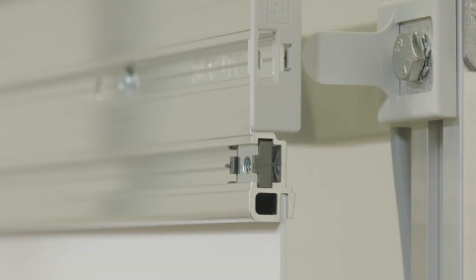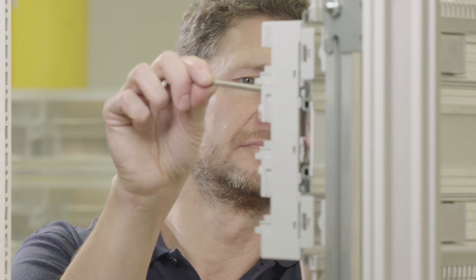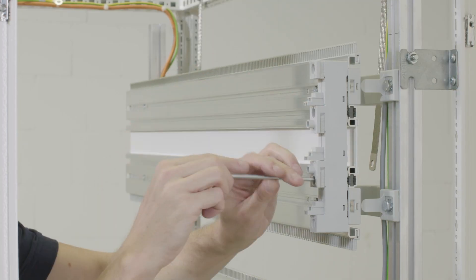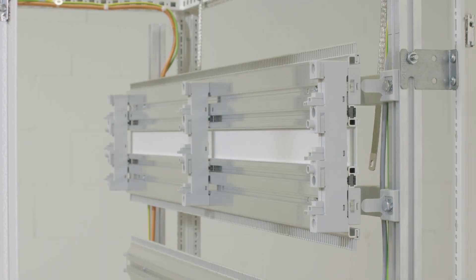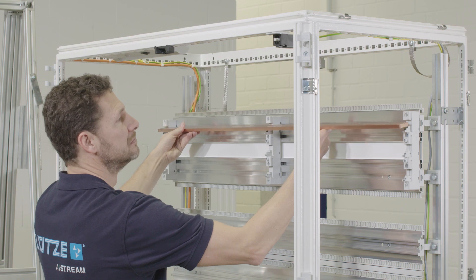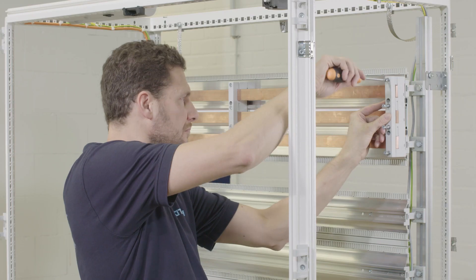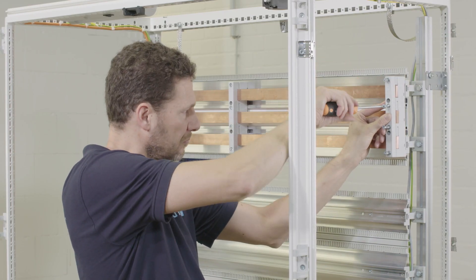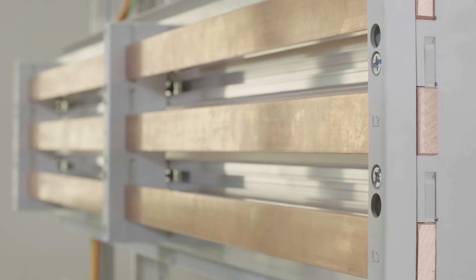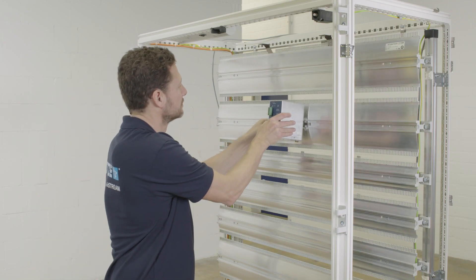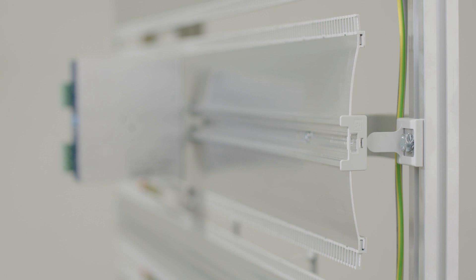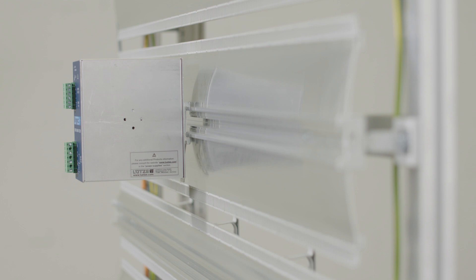Sliding nuts allow easy installation, for example of the busbar system as shown in this example. For control cabinets that are in series, a continuous busbar system can be easily created. A wide variety of DIN rail units can be simply snapped on, taking up a minimum of space. Due to the rounded profiles, larger components can also be attached.